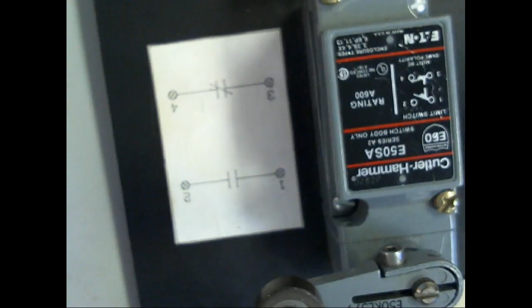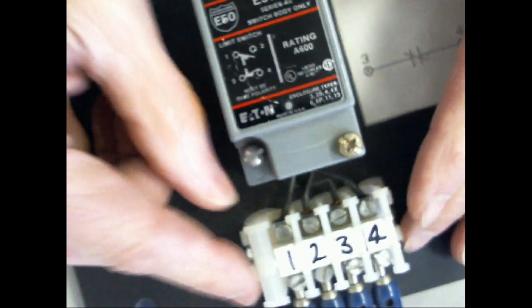It has one set of normally open contacts and one set of normally closed contacts. This shows the manufacturer numbers, which electricians use to know how to wire things up. On ours, they brought these manufacturer numbers out to these terminals, so instead of taking off the cover and wiring it up down there, we can wire them up right here.